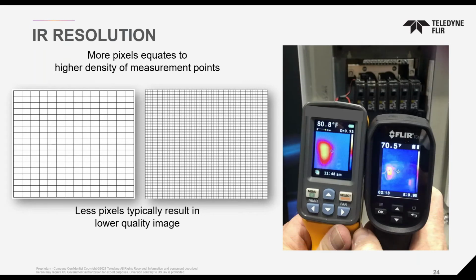Here's two cameras side by side: the Flir camera on the left, competing camera on the right—or the Flir camera on the right, competing camera on the left. With a little more resolution, we can actually see where this fuse is heating up. We can almost count the fuses and definitely identify where it's coming from. We can even see the cable, or this wire, coming into this panel.